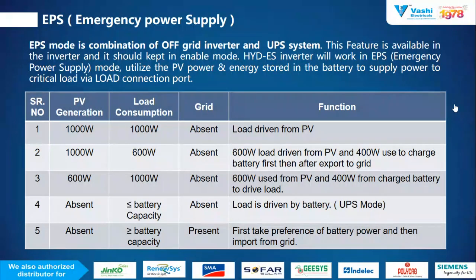It is considered UPS mode because your PV power as well as grid power is not available. The last point: PV generation is absent and your grid is present. In this condition, if your load consumption is higher compared to the battery capacity, then first preference is taken from the battery power and then power is imported from the grid. So these are the 5 conditions for when it is working in UPS mode and when it is operating in off-grid mode. Next.